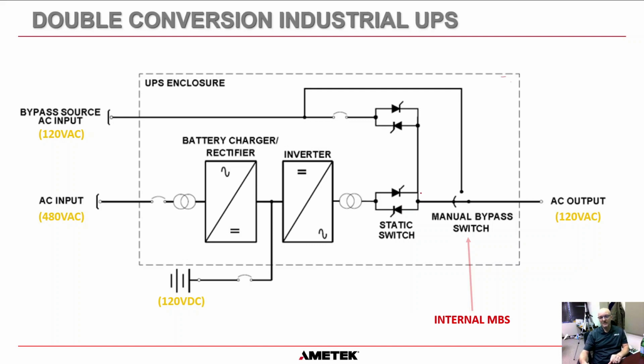The static switch is an electronic switch, which is actually drawn identical to what it actually is. It has two SCRs back to back connected in inverse parallel. And what that allows us to do is, if there is a sine wave on this side of the static switch, and we send a signal to the gates of both of those SCRs, that turns that switch on electronically. There are no moving parts in it whatsoever. It's just using the semiconductor devices, which are the SCRs, and it allows the sine wave to pass through to the other side of the switch.